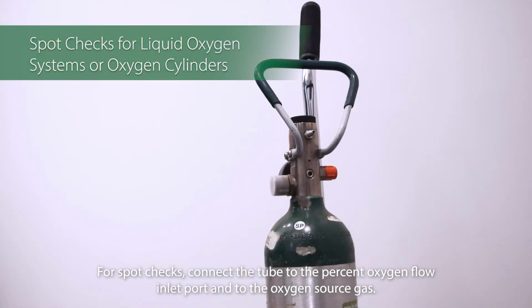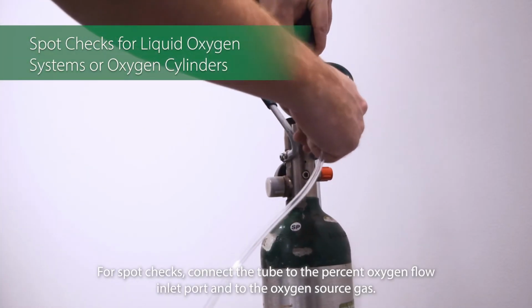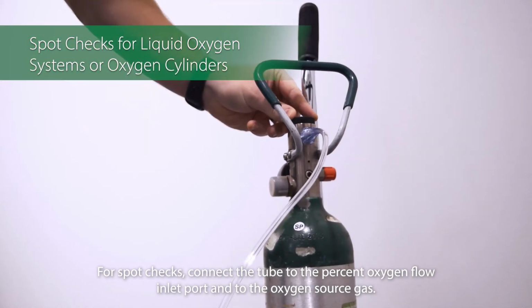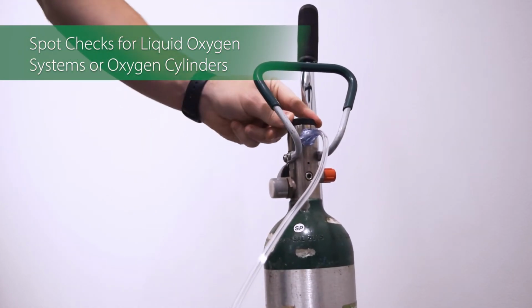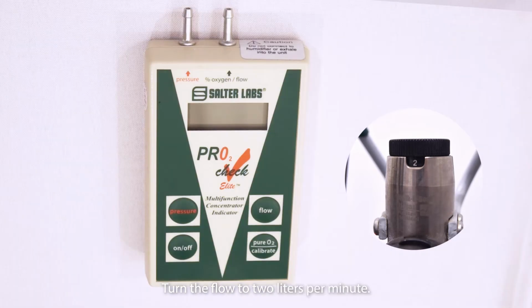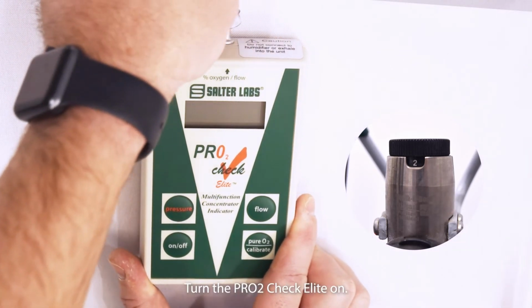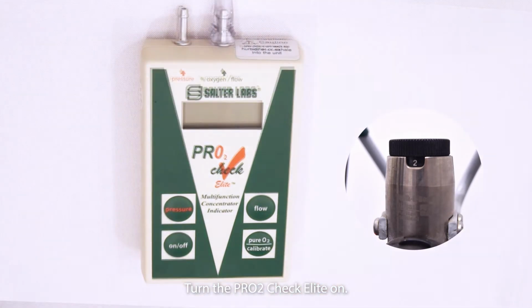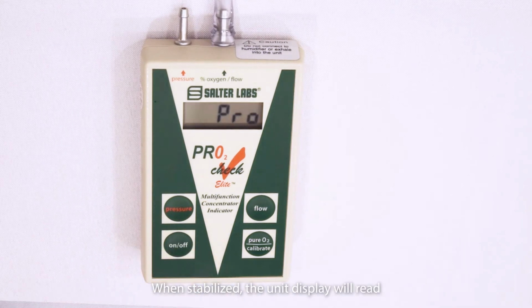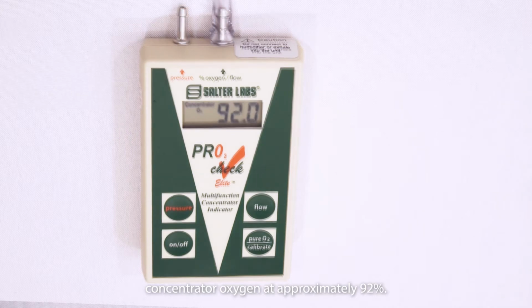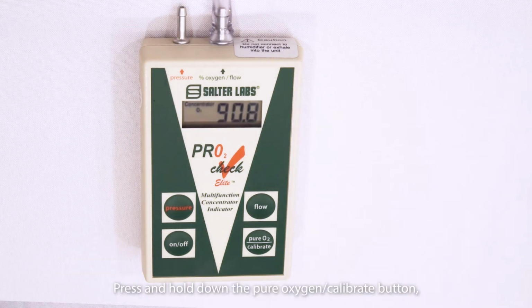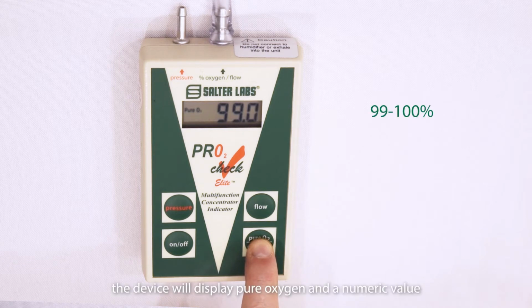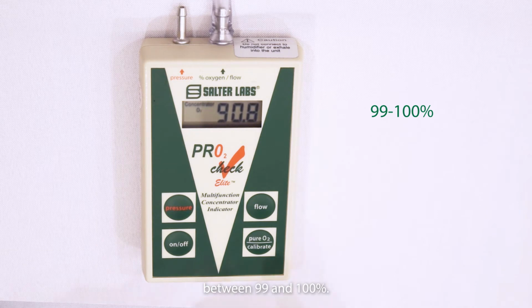For spot checks, connect the tube to the % oxygen flow inlet port and to the oxygen source gas. Turn the flow to 2 liters per minute. Turn the PRO2 Check Elite on. When stabilized, the unit display will read concentrator oxygen at approximately 92%. Press and hold down the Pure Oxygen Calibrate button. The device will display pure oxygen and a numeric value between 99 and 100%.